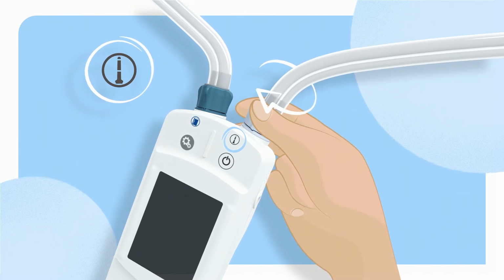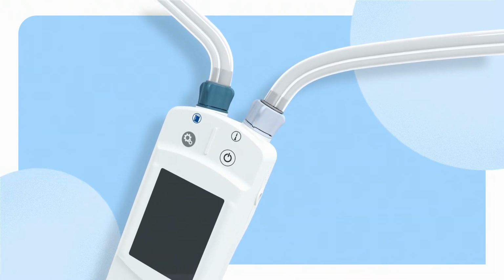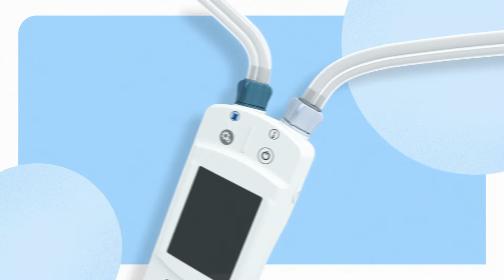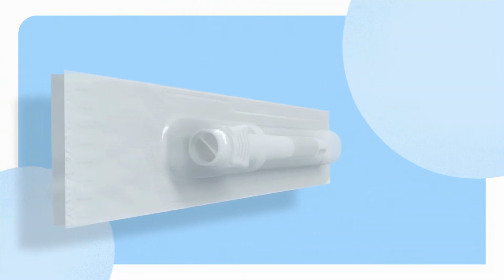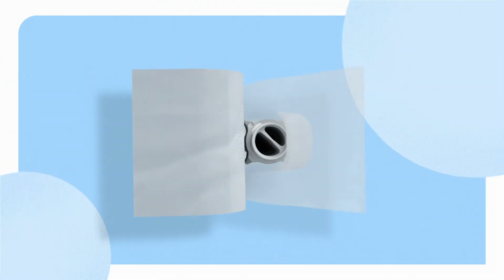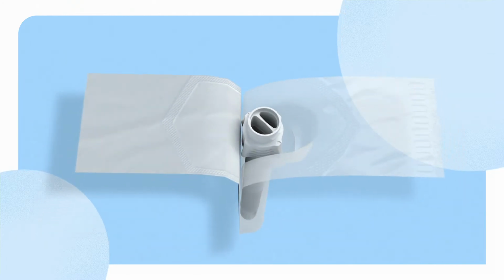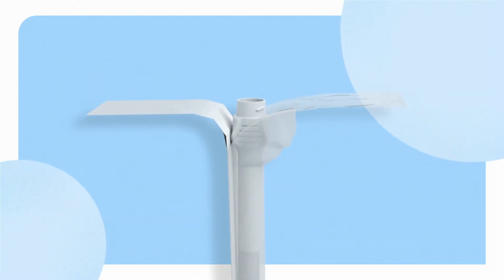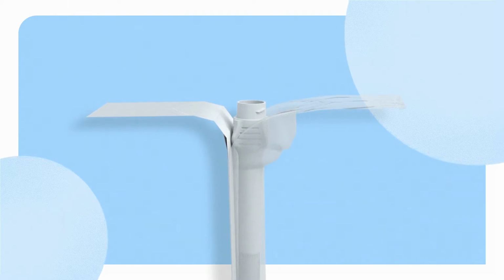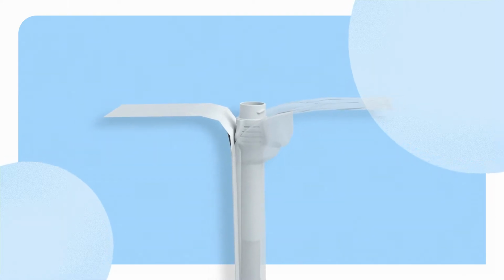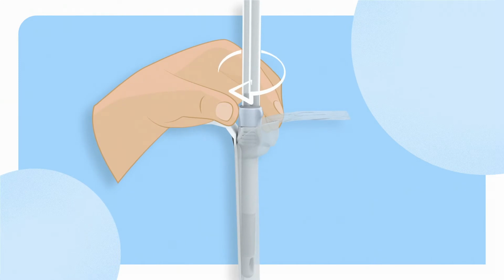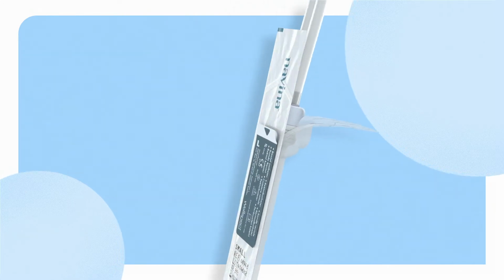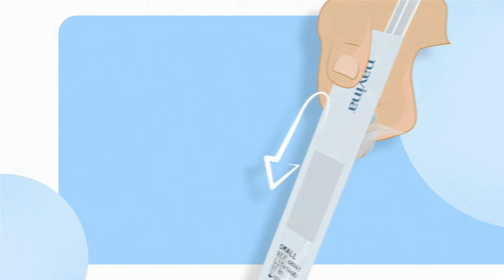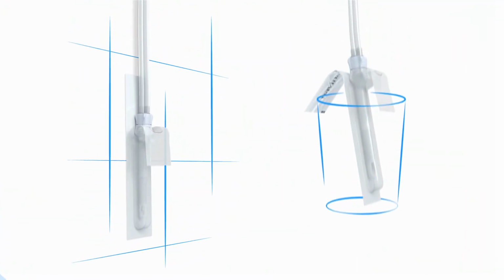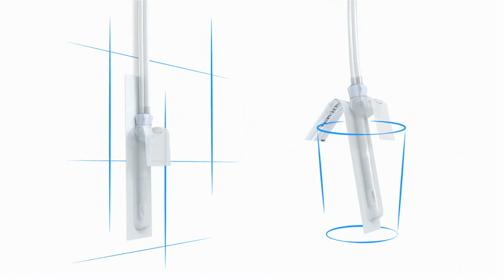Connect the light blue connector to the control unit. Then connect the rectal catheter. To do so, first peel the catheter packaging open 2 to 3 centimeters to expose the catheter connection. Don't remove the packaging yet, you'll need it on for a few more steps. Attach the tube with the white connection to the rectal catheter. The packaging can be attached to a vertical surface or placed in a tall glass. Ensure the rectal catheter is within easy reach.